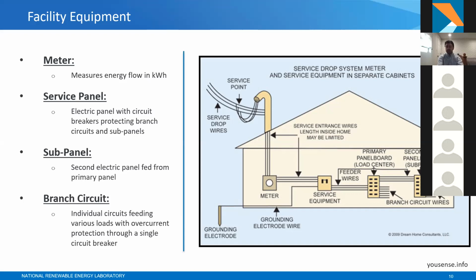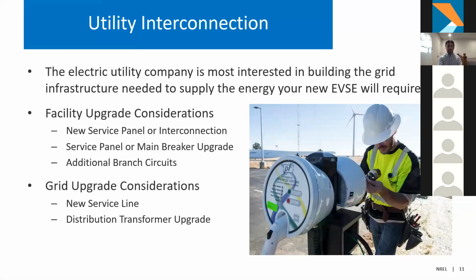And then it also is a great picture that highlights that branch circuit and how some of those branch circuits step out of those service panels. And actually some service panels have circuits that feed a sub panel. So if you have multiple service panels or circuit boxes at your facility, make sure that you understand the structure of each of them. If you're upgrading one, you'll most likely have to upgrade another one up the line if they're connected and working together. Next slide. Oh, back just one, yeah.